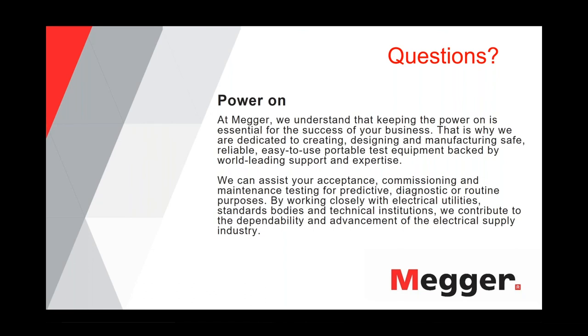If the junction box is in a really, really bad condition, think about surface leakage, then it's the same as with a termination. If internally you have additional paths on surfaces where you can have additional creepage, then the tan delta value is always influenced, or, as Javier showed in the example, water. A splice can have an influence if it's full of water, because then you see that the tip-up suddenly stops or goes flat from 1 to 1.5, or it goes negative. That's a typical indication of local moisture somewhere in the cable. And these junction boxes can also be full of water if it rained and it just fills up, as you have sometimes, then you could also under certain circumstances have influences there.